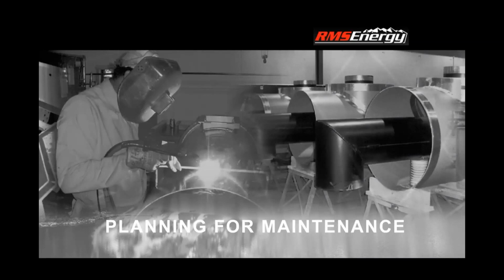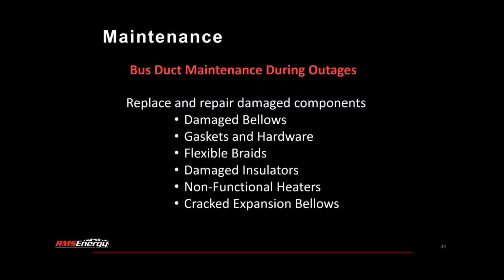So with these critical components in mind, we'll talk a little bit about planning for maintenance and what some considerations are before you enter an outage. So generally, again, maintenance is maintaining the critical components within your bus system and repairing any damage once you find it.